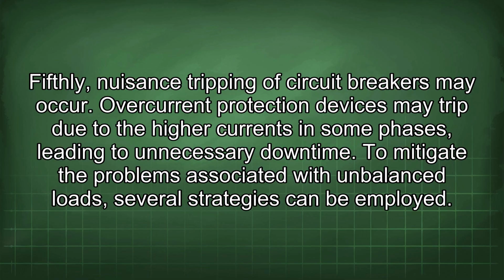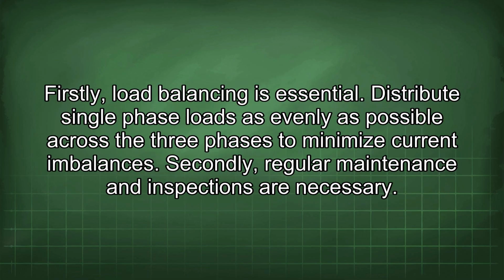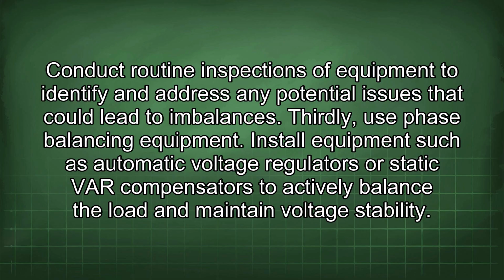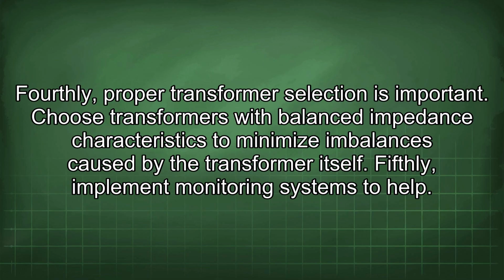To mitigate the problems associated with unbalanced load, several strategies can be employed. Firstly, load balancing is essential. Distribute single-phase loads as evenly as possible across the three phases to minimize current imbalances. Secondly, regular maintenance and inspections are necessary. Conduct routine inspections of equipment to identify and address any potential issues that could lead to imbalances. Thirdly, use phase balancing equipment. Install equipment such as automatic voltage regulators or static VAR compensators to actively balance the load and maintain voltage stability. Fourthly, proper transformer selection is important. Choose transformers with balanced impedance characteristics to minimize imbalances caused by the transformer itself.